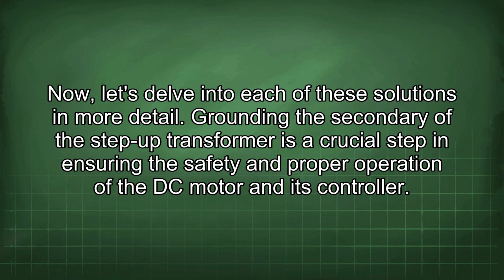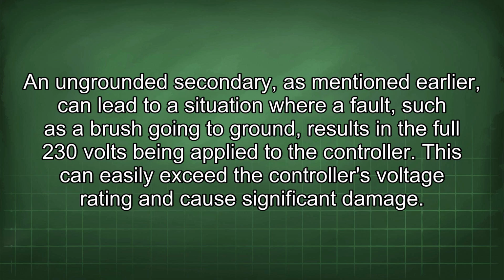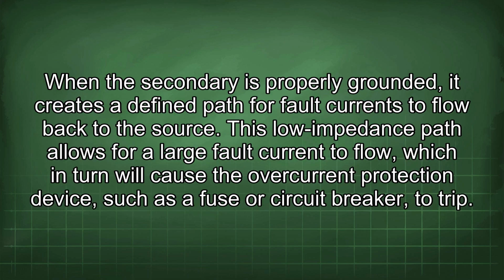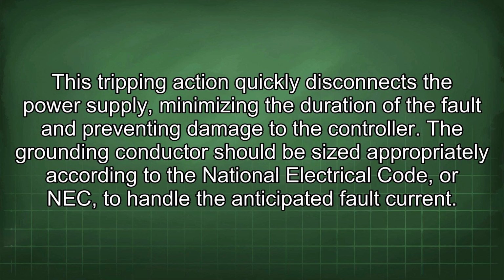Grounding the secondary of the step-up transformer is a crucial step in ensuring the safety and proper operation of the DC motor and its controller. An ungrounded secondary, as mentioned earlier, can lead to a situation where a fault, such as a brush going to ground, results in full 230 volts being applied to the controller. This can easily exceed the controller's voltage rating and cause significant damage. When the secondary is properly grounded, it creates a defined path for fault currents to flow back to the source. This low impedance path allows for a large fault current to flow, which in turn will cause the overcurrent protection device, such as a fuse or circuit breaker, to trip. This tripping action quickly disconnects the power supply, minimizing the duration of the fault and preventing damage to the controller.